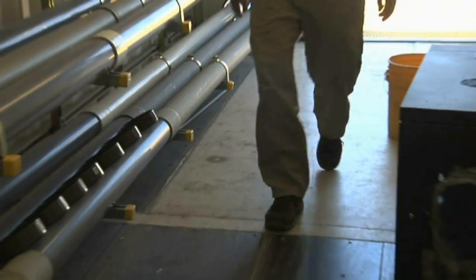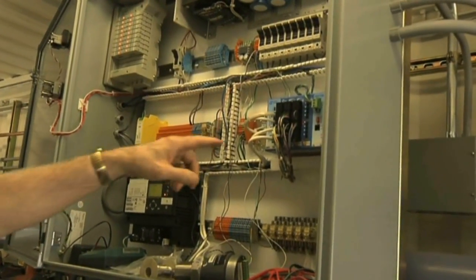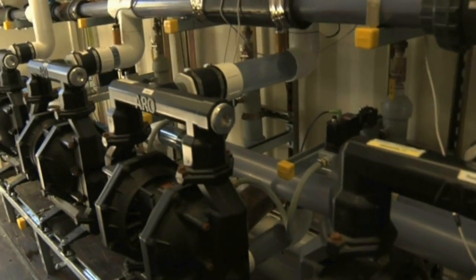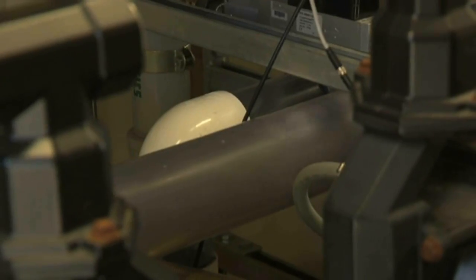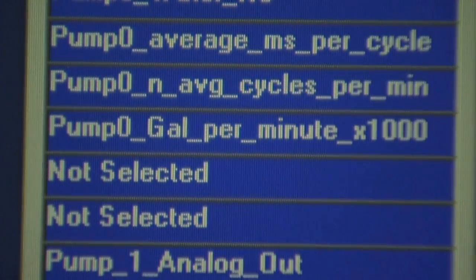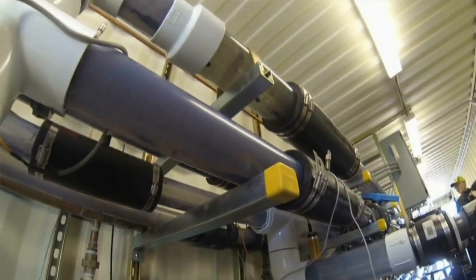This is the inside of the laboratory container, and we have a computer, a programmable logic controller in a case here, and we have four pumps. The pumps behind me are positive displacement pumps as well as being air-operated. That means we can use them to measure the flow rate of the water in the pipes. The computer can keep track of how many pump cycles there are and record how many gallons per minute have been sent to the stormwater technologies.